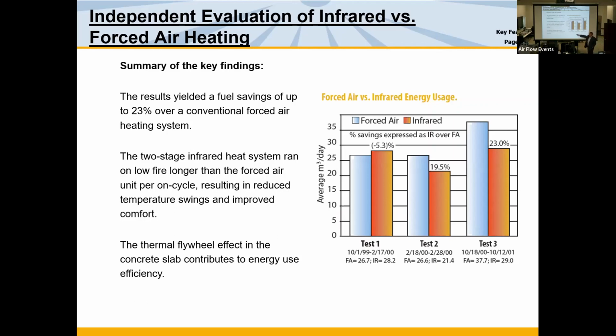With the flywheel effect, when we were switching every week, let's say we switched on a Sunday, Monday or Tuesday, the infrared that was still trapped on the floor was benefiting the unit heaters. By the end of the week, when we went back to switch again, the infrared heaters had to make up for what the hot air heaters couldn't put in the slab. So we realized we had to adjust it. The next year it ran all hot air, the next year it ran all infrared. And then we zeroed it out.